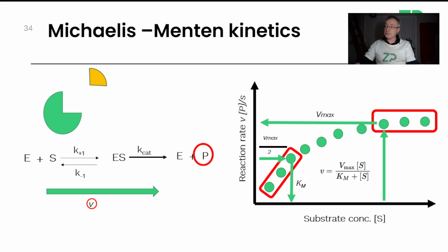I'm not going to discuss them here, but it's just to emphasize that the signal from an enzyme biosensor is very well modeled by the Michaelis-Menten equation. When you plot signal, or rate of reaction, which is the production of P as a function of time, there are two properties that come out of this curve. Vmax is super useful because it tells us how much signal we can really expect to get out of this particular biosensor. And Km tells us what the linear range is for that particular biosensor.